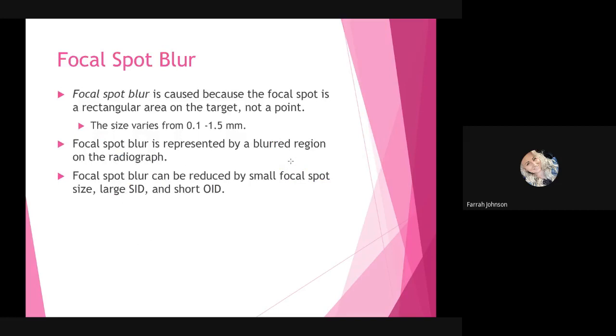And then lastly, that brings us to focal spot blur. So this is caused because the focal spot is a rectangular area on the target and not a point. And the size can vary anywhere from 0.1 to 1.5 millimeters. Now, focal spot blur is represented by a blurred region on the radiograph, and it can be reduced by a small focal spot size using a larger SID and a shorter OID.